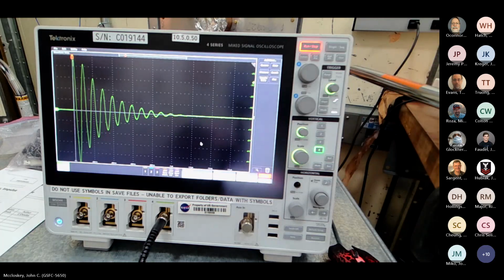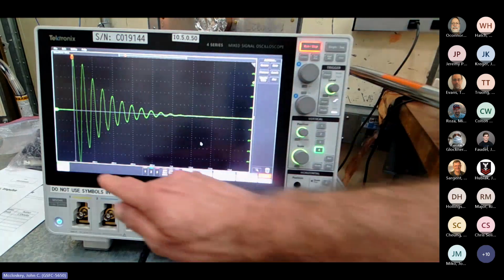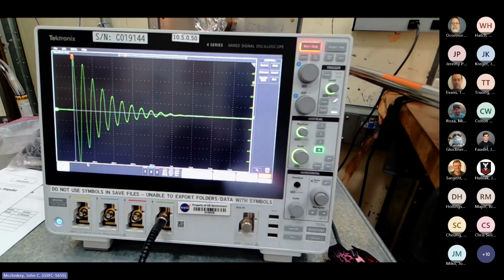Turn that off. So if I wanted a little better resolution around that peak, I might put another 20 dB of attenuation so that it's 500 millivolts. But here we are. We'll leave it like this. So the lower peak is coming right up against that limit, or the edge of the display, of -5 volts. The upper peak is maybe just shy of that. We could tweak that, but you get the idea. It's giving you that 5 volts, but then prior to the 40 dB of attenuation, that's your 500 volts. And then into 50 ohms, that's your 10 amps.